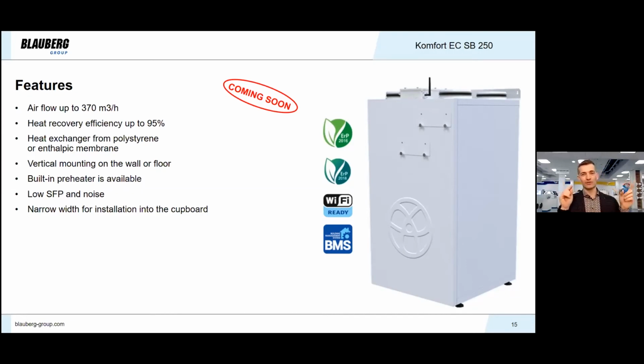We call it Komfort EC SB 250, but the real maximum airflow of the unit is a little bit higher. It is up to 370 cubic meters per hour at 0 Pascal. According to our internal tests, we have reached up to 95% heat recovery efficiency at some small airflow. Later I will show you the diagram. 2 heat exchangers can be applied in this unit. The first one is made from polystyrene, and it gives us the highest efficiency that we can reach. The second is made from enthalpic membrane. Heat recovery efficiency is a little bit lower, but thanks to the recuperation of humidity, it gives a little bit higher level of comfort.